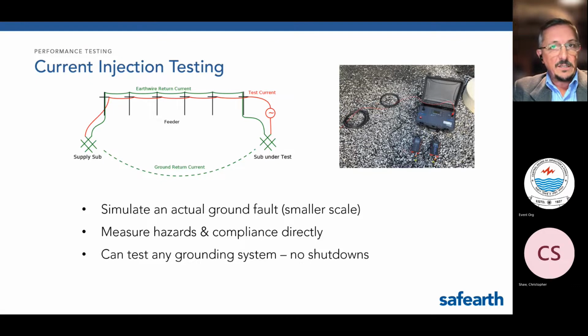To allow it to be measured, even in a live station with a lot of electrical noise, the current is injected at a chosen frequency away from the power system frequency and any other noise. Highly sensitive current and voltmeters are used, tuned to the injected frequency and with very high rejection of other noise, such as induction and standing voltages.